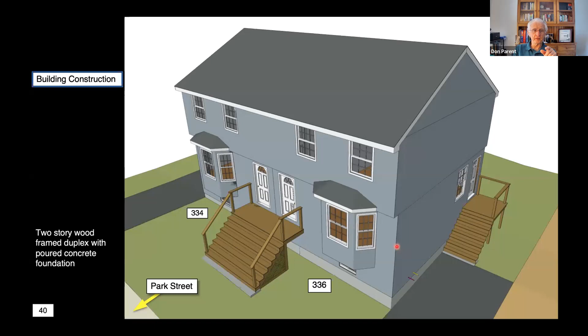Here what you see is the basement of the building and the first floor. What we found was that it's a hot air system where the furnace is taking air from the return air duct, heating it, and returning it back to the floors up above. And just prior to the incident, Lawrence, Mass experienced like a week of 0-degree weather. So things got really cold, and the furnaces were running full time during that period.